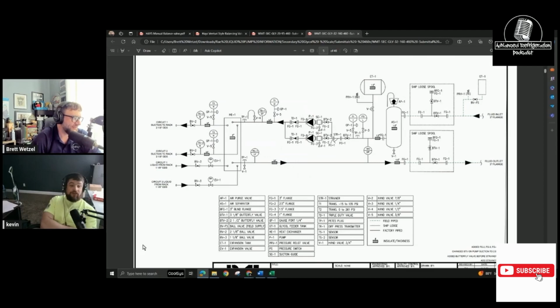This is the first time I've ever gotten a rack that actually ran in a factory before it got shipped out. Wow. For 3 weeks. I guess they wanted to make sure it was working right. The other weird thing about this rack, which I've seen before but never really seen utilized, is this is a dual circuited heat exchanger. Yeah, all the Costcos are like that. Where it has one glycol line going in, one glycol line going out, but then you have two liquid lines and two suction lines coming out of the heat exchanger.